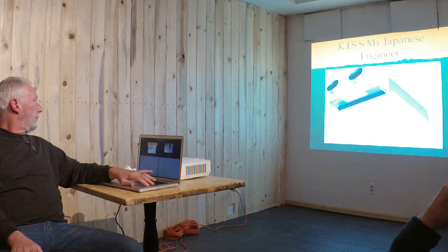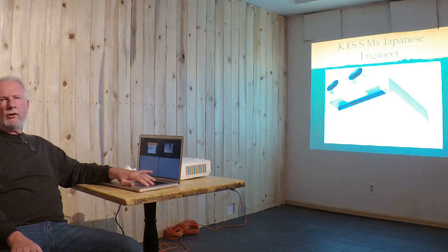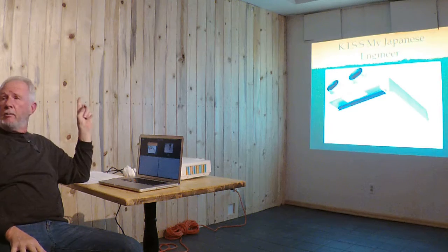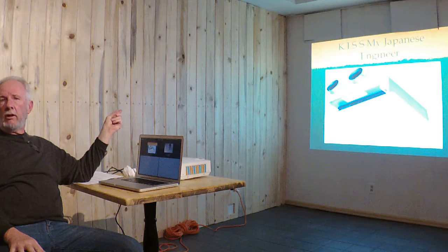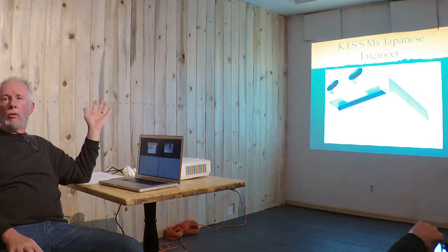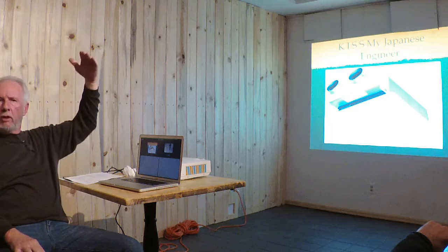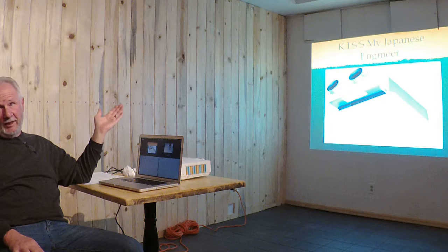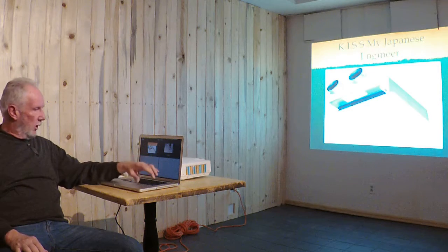My favorite is a Panasonic ERV unit — about 2 by 2 feet, similar to a large bathroom fan. It goes directly through your floor joist and outside, placed in a hallway or main living area. These cover about 1,000 to 1,200 square feet depending on layout; for big houses, use them on multiple levels. They run between $500 and $750 plus installation — cheap, easy, highly effective. They have a humidistat and timers. Really smart and works incredibly well.